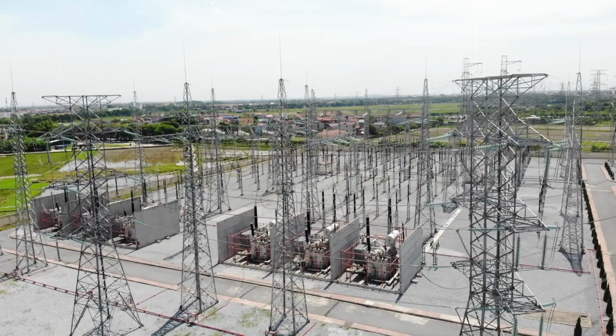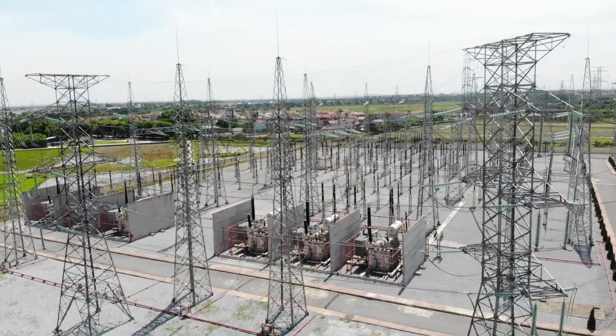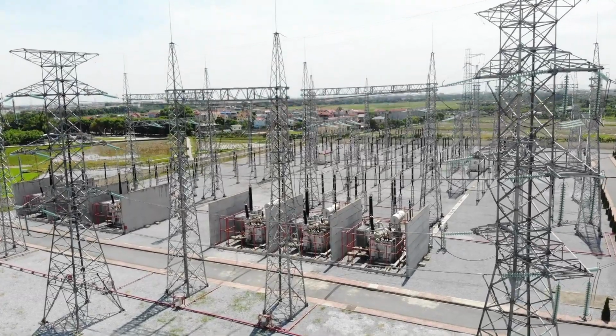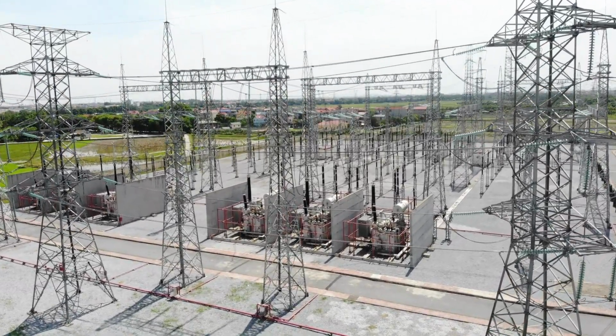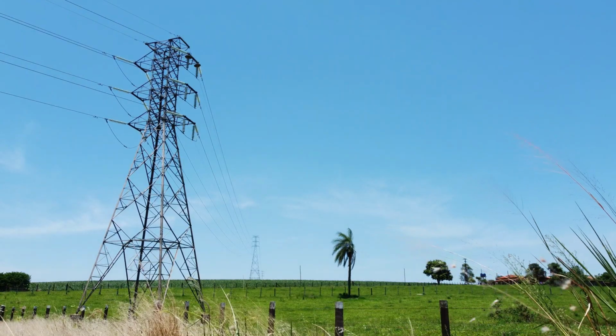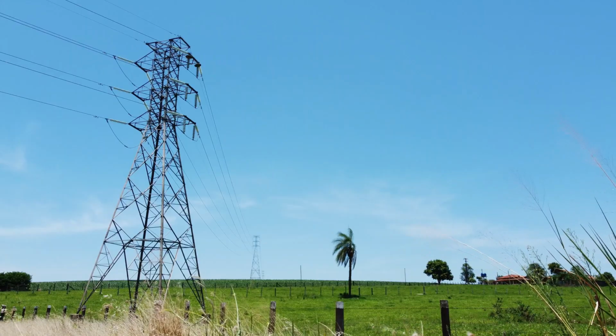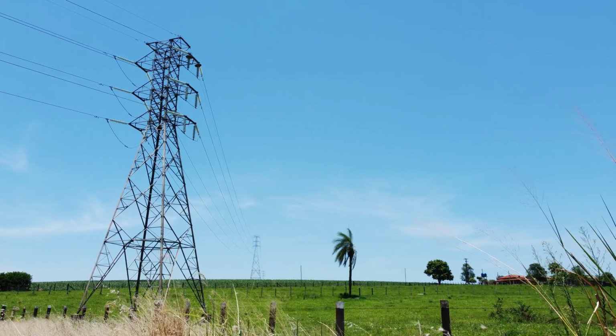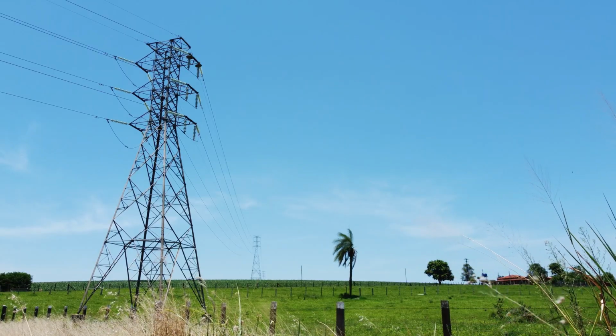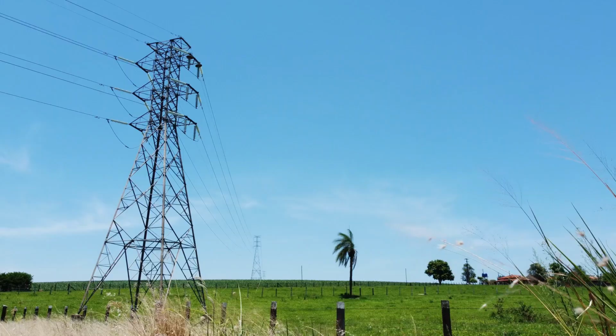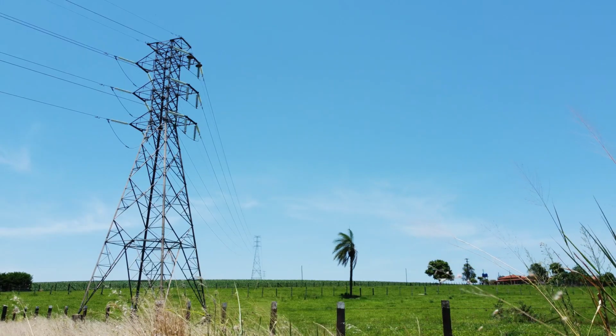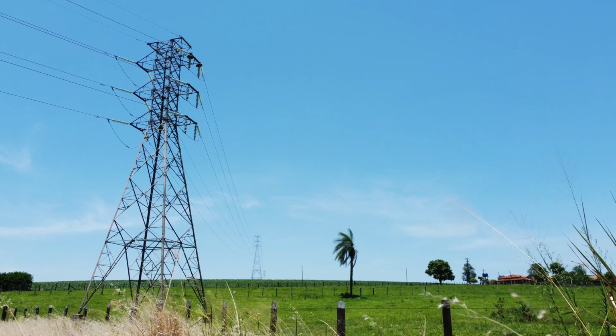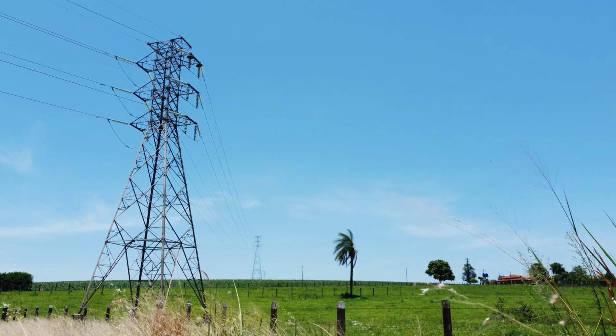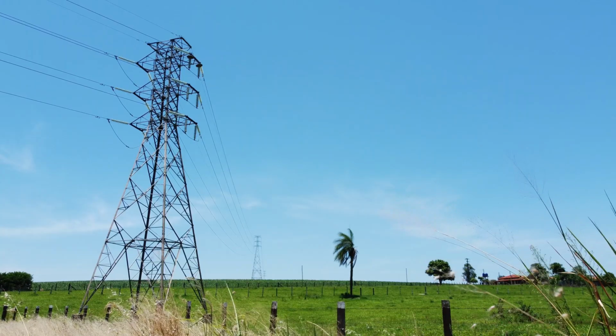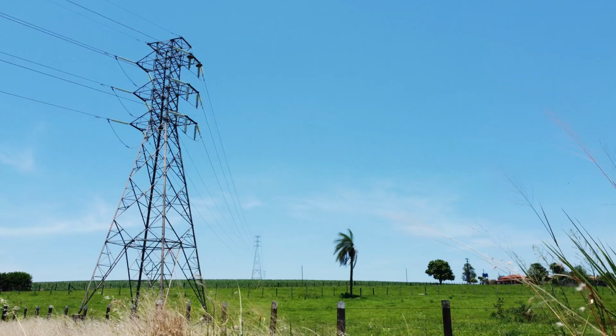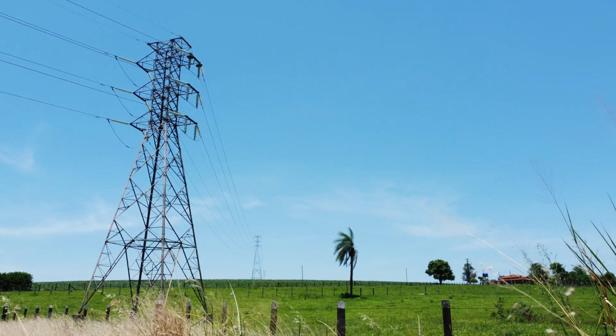Another essential function of substations is voltage transformation. Electricity generated at power plants is typically produced at relatively low voltages. To efficiently transmit power over long distances, the voltage must be increased to extremely high levels such as 138,000, 230,000, 500,000, or even 750,000 volts. Higher voltage reduces energy losses during transmission. Near cities and residential areas, substations perform the opposite process by reducing transmission voltage to distribution levels suitable for local networks. In many countries, distribution systems operate around 13,800 volts before the electricity is finally reduced again for household use.